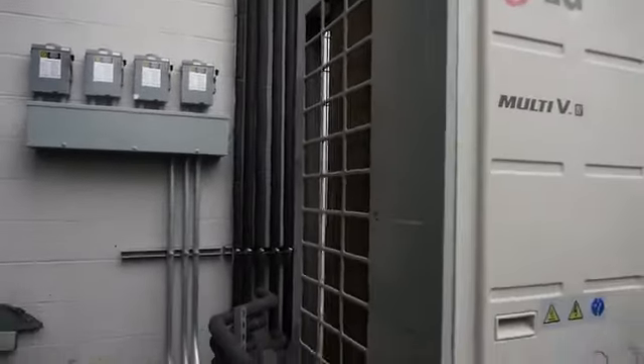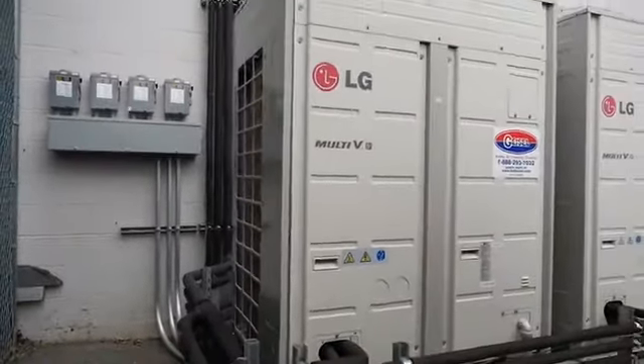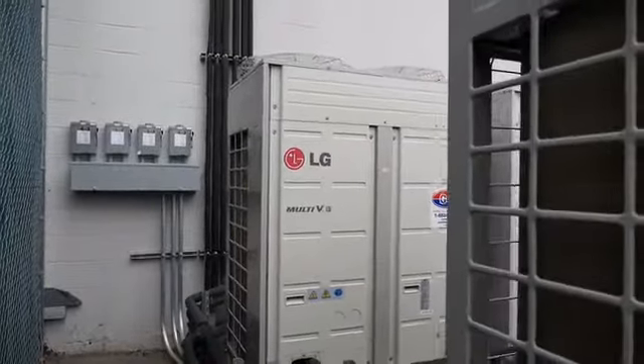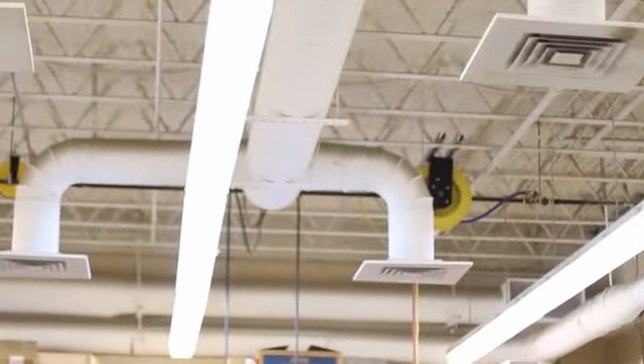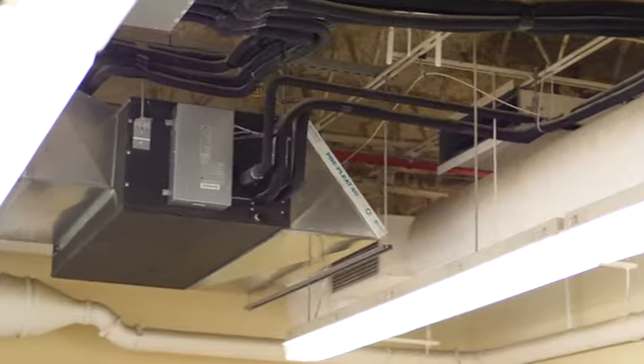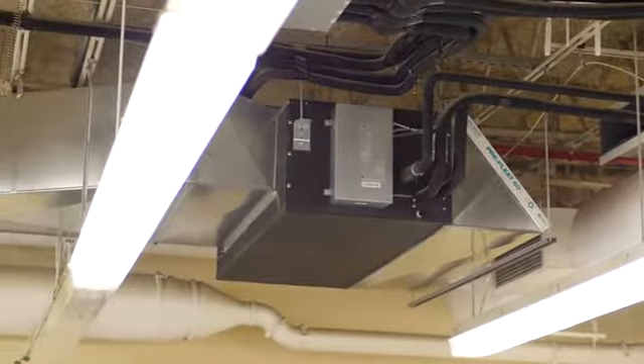It was a very smooth transition. They were still able to keep their old system running as we transitioned to the new system. So a combination of things were used. Where we could, we reused the existing ductwork just to save on cost, and we plugged our ducted fan coil into the place of the VAV box.